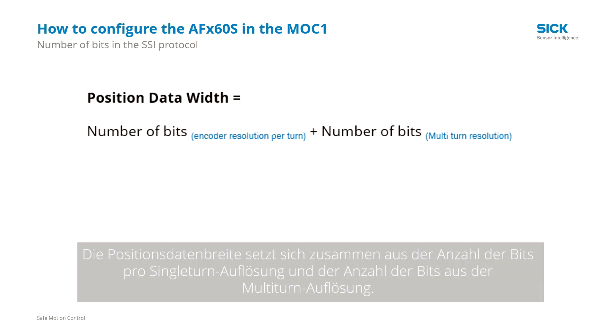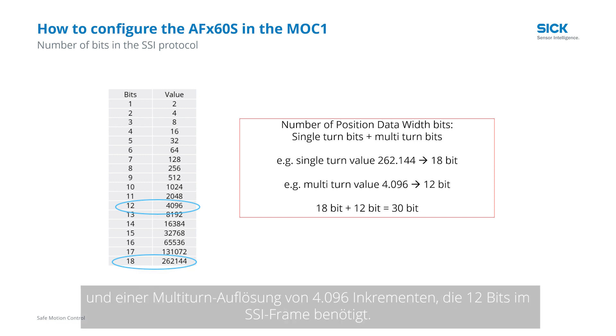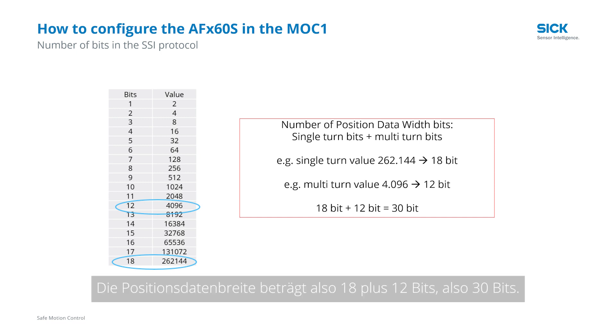The position data width is built up from the number of bits per single turn resolution plus the number of bits from the multi-turn resolution. In our example, we use a multi-turn encoder with a single turn resolution of 262,144 increments, which needs 18 bits in the SSI frame, and a multi-turn resolution of 4,096 increments, which needs 12 bits in the SSI frame. So the position data width is 18 bits plus 12 bits equals 30 bits. We change back to the Safety Designer, fill in this value in the position data width, and push enter.